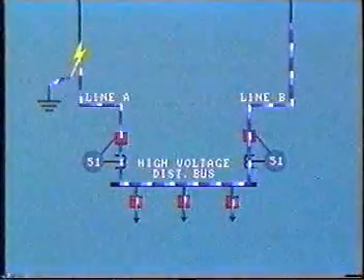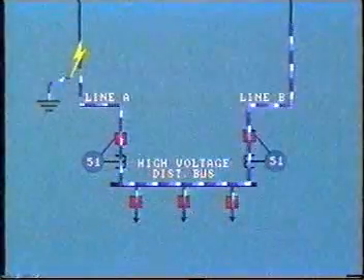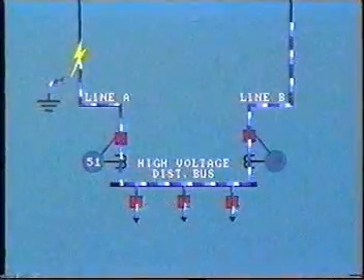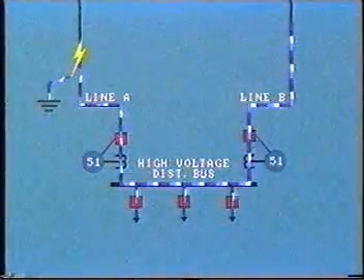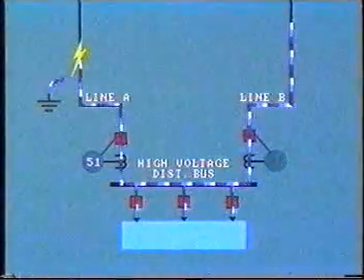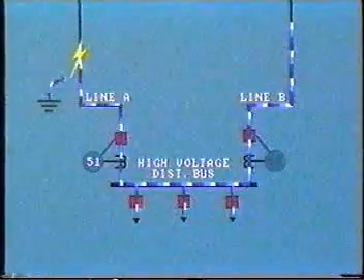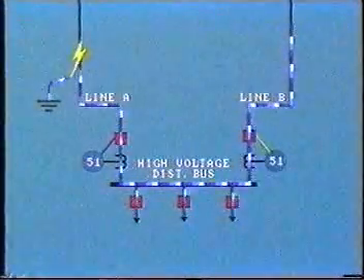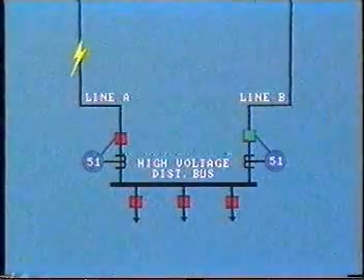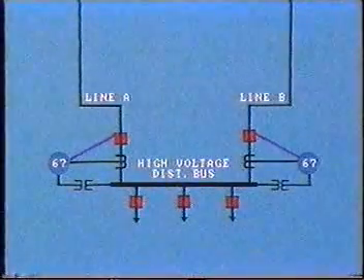But the current in line B has also increased to feed the fault. Therefore, its own overcurrent relay will also sense the high-level current and commence the tripping process. In fact, line B is also feeding the distribution load and therefore passes greater current than A. If the B relay trips out line B, the substation is left without any power supply at all. We can avoid this by using directional overcurrent relays, device number 67.